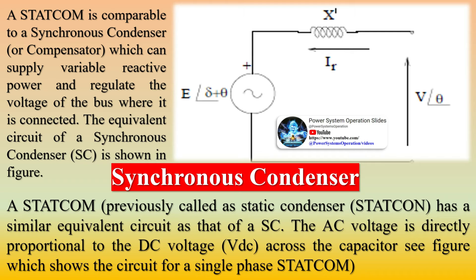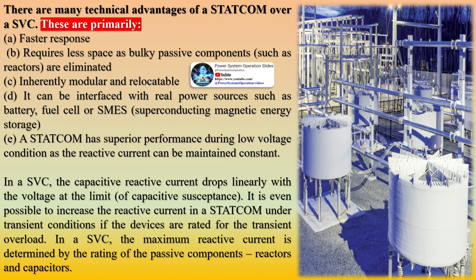STATCOM can be based on a voltage-sourced or current-sourced converter. One configuration uses a voltage-sourced converter driven by a DC voltage source capacitor, effectively an alternating voltage source behind a coupling reactance, controllable in magnitude. It can be operated over its full output current range even at very low — typically 0.2 PU — system voltage levels. It requires fewer harmonic filters and capacitors than an SVC, and no reactors, making it significantly more compact.